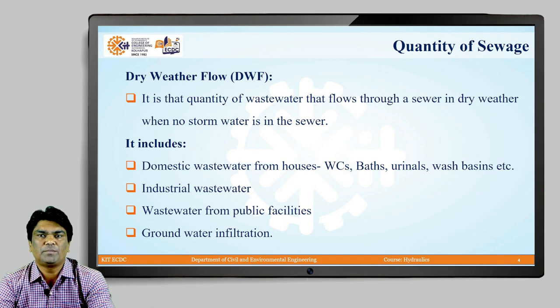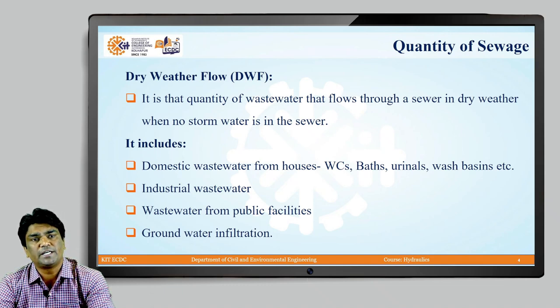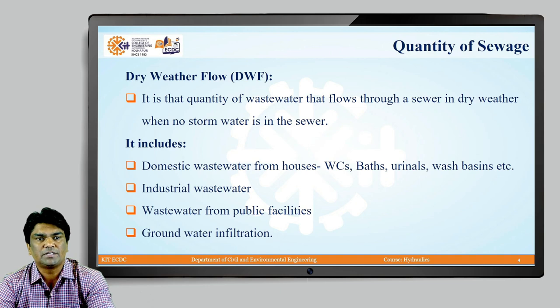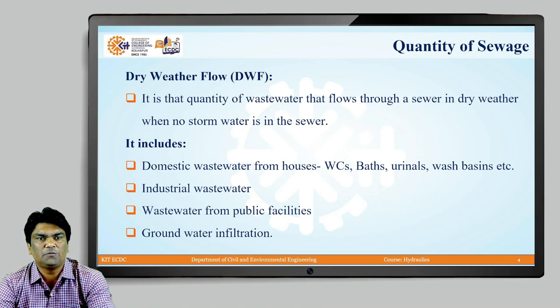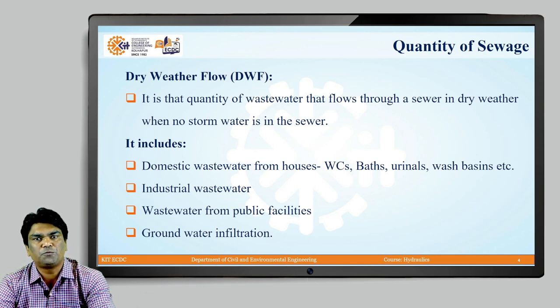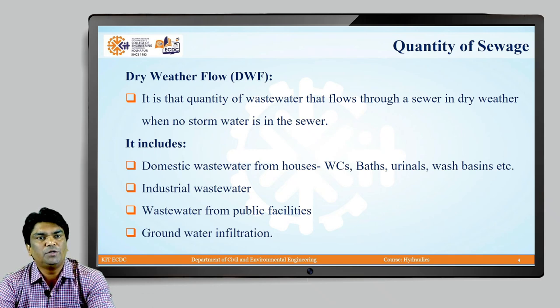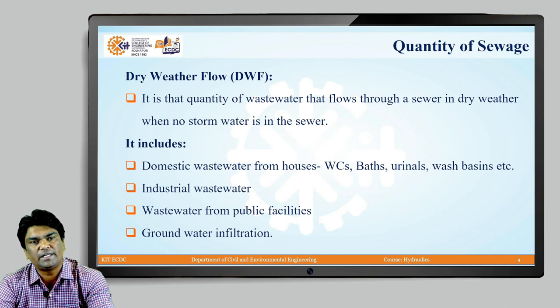Moving to the next part, let us discuss the quantity of sewage — how to quantify it. Sewage is nothing but waste water generated from various sources, and it also includes infiltrated groundwater. There are two key terms: dry weather flow and wet weather flow. Dry weather flow is that quantity of waste water that flows through a sewer in dry weather conditions when no storm water is in the sewer — essentially the sanitary flow.